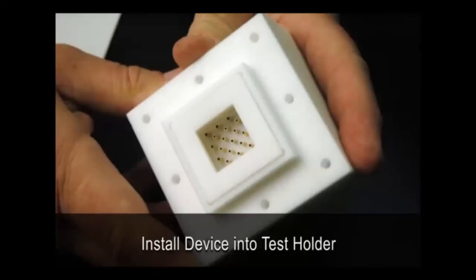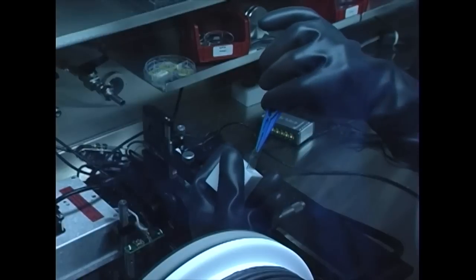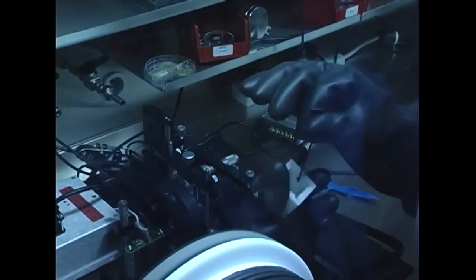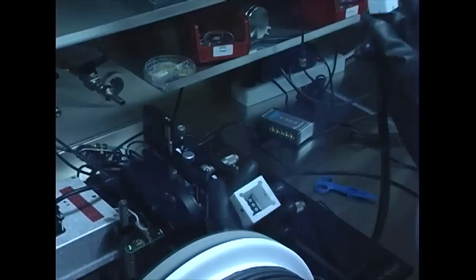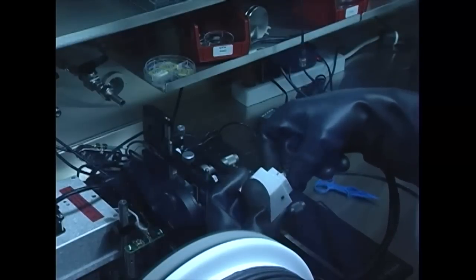The mask is removed and the device is placed in the test apparatus. We transfer the device into the test holder. The ITO layer forms one continuous conductor, while the cable connector has gold pins that match up with each PV test contact point. The test mount is placed in the apparatus and the cable is attached to the computer input jack.